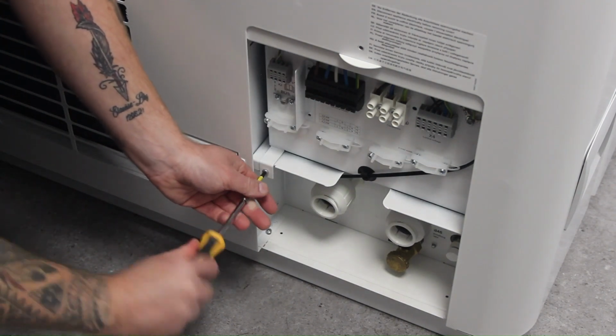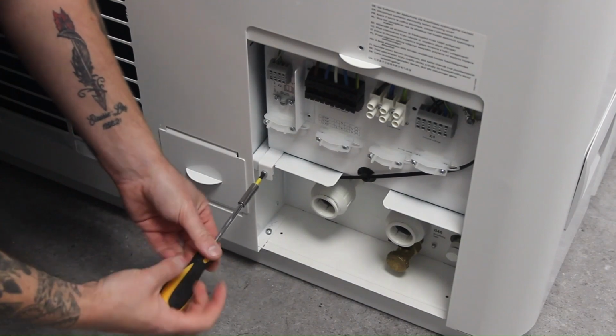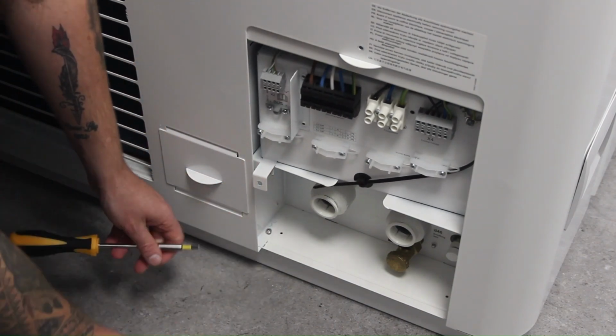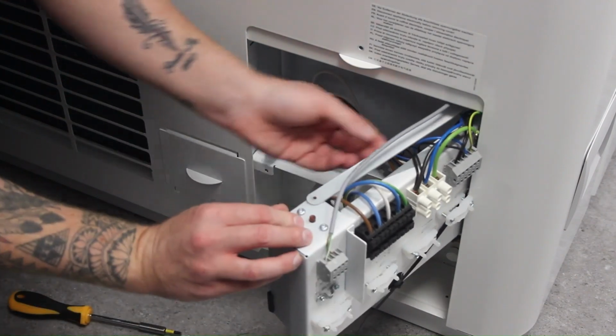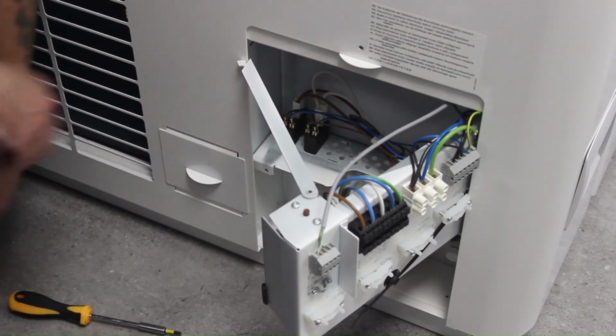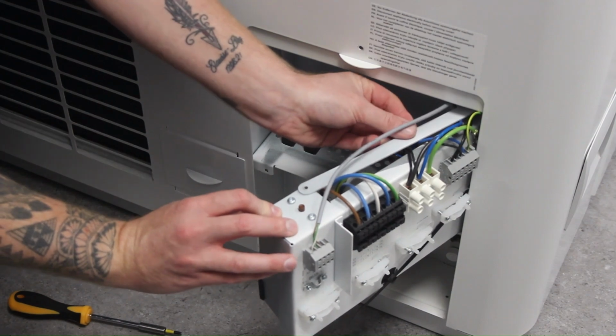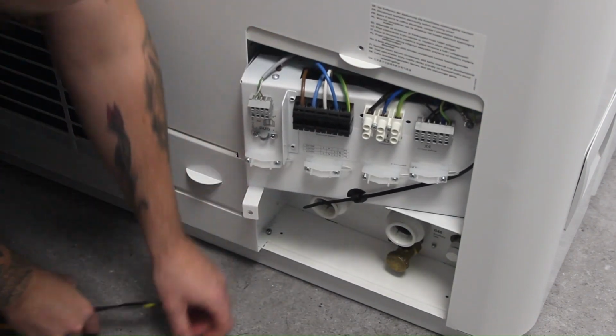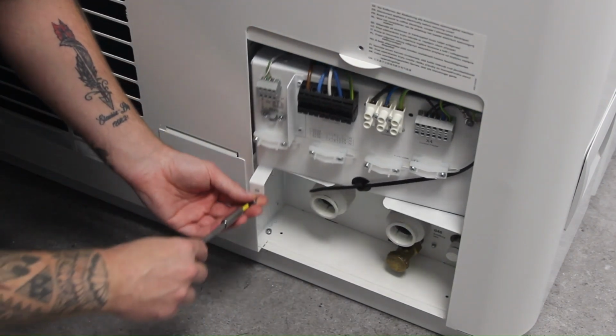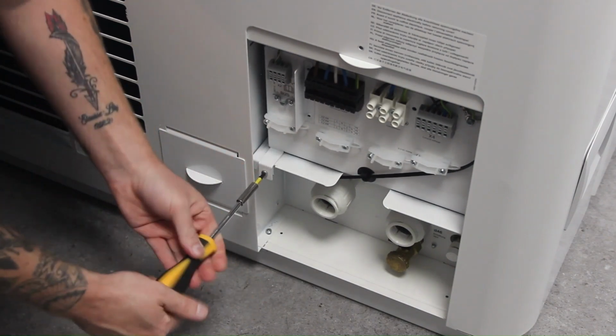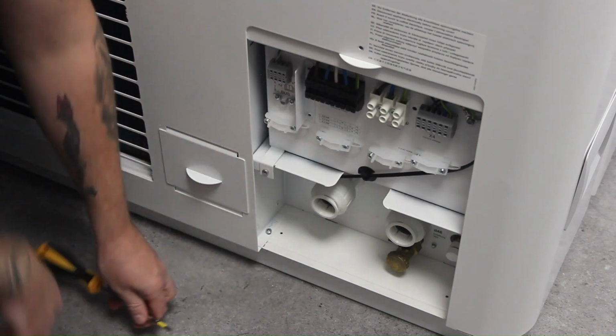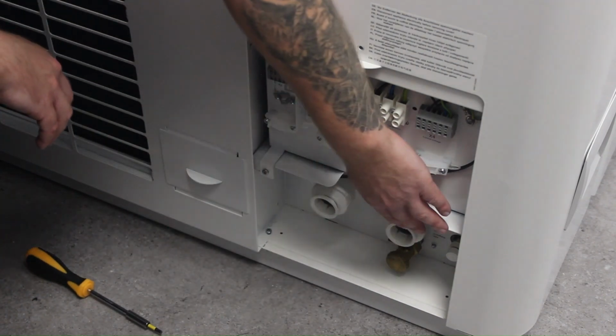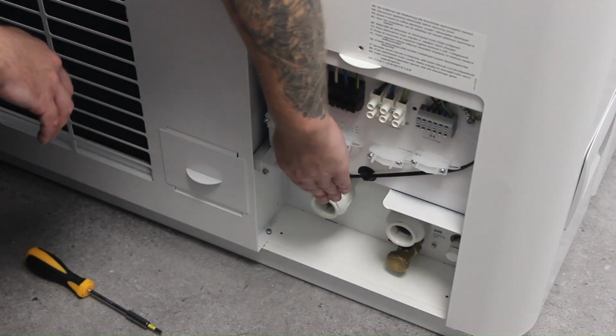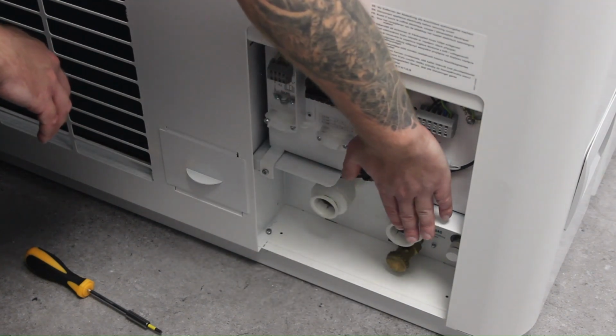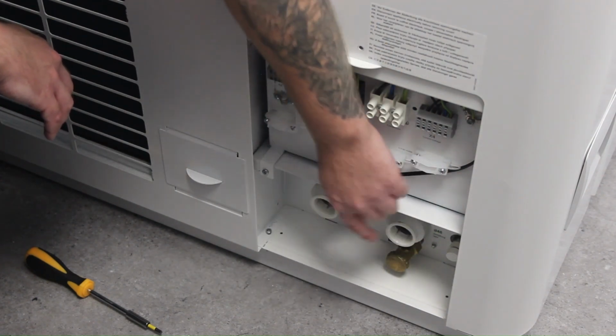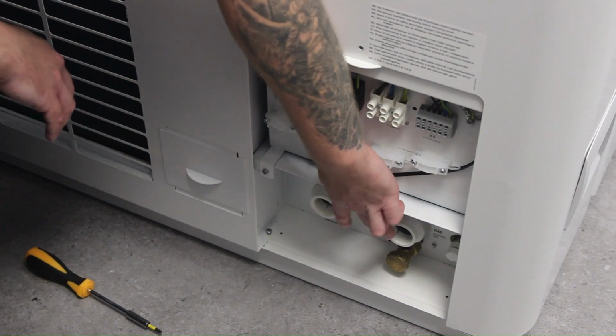You can remove the Torx screw and your electrical panel opens up to make it easier to access. Below our electrical connections, we have our hydraulic connections. These are 28mm connections. We have our flow and our return. You will need 100mm pipe spacing between the flow and return.